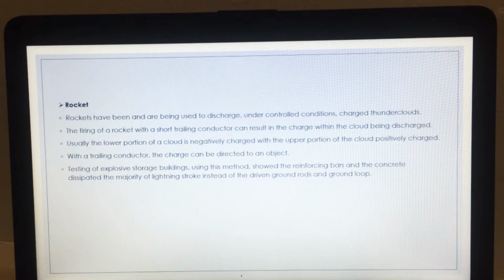The firing of a rocket with a short trailing conductor can result in the charge within the cloud being discharged. Usually the lower portion of the cloud is negatively charged, with the upper portion of the cloud positively charged. With a trailing conductor, the charge can be directed to an object. Testing of an explosive storage building using this method showed the reinforcing bars and the concrete dissipated the majority of the lightning stroke instead of the driven ground rods and the ground loop.